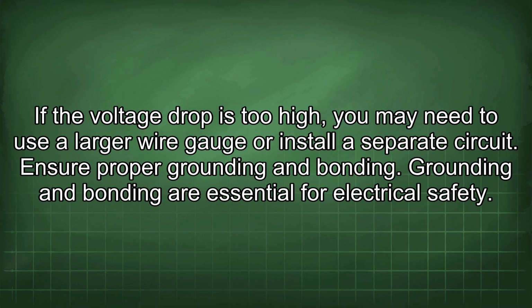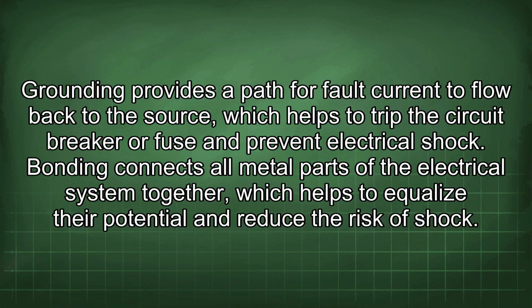Ensure proper grounding and bonding. Grounding and bonding are essential for electrical safety. Grounding provides a path for fault current to flow back to the source, which helps to trip the circuit breaker or fuse and prevent electrical shock. Bonding connects all metal parts of the electrical system together, which helps to equalize their potential and reduce the risk of shock.